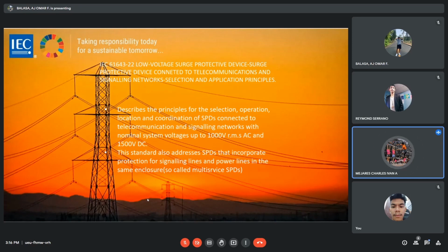IEC 61643-22, low voltage surge protective devices connected to telecommunications and signaling networks, selection and application principles. Describes the principles for selection, operation, location, and coordination of SPDs connected to telecommunications and signaling networks with nominal voltage up to 1000 volts RMS AC and 1500 volts DC. These standards also address SPDs that incorporate protection for signaling lines and power lines in the same enclosure, called multi-service SPDs. Next.